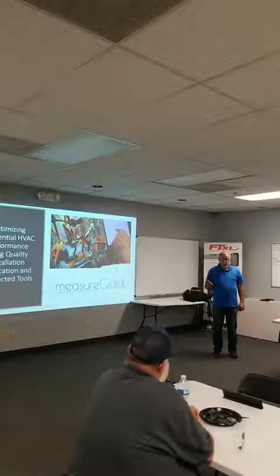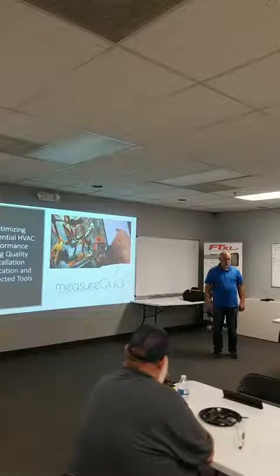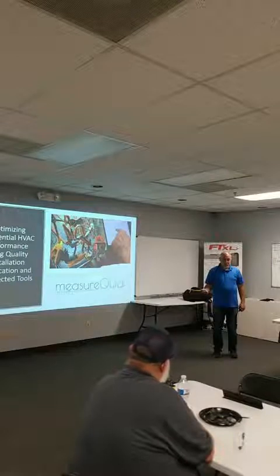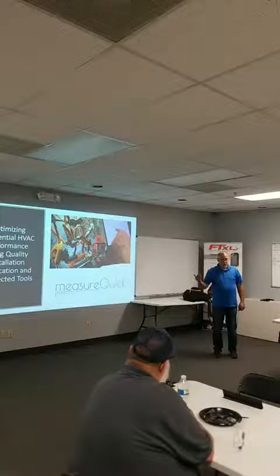If you're looking at a system with 75 degree return air, we know that typically the evaporator coil is 35 degrees colder. 75 minus 35 is a 40 degree evaporator. A 40 degree evaporator would be about 118 pounds of pressure, right? If you have a 40 degree evaporator and 10 degrees required superheat, 40 plus 10 is a 50 degree suction line temp, right? Same thing if we had a 100 degree condensing temp and were supposed to have 10 degrees of subcooling. 100 minus 10 is 90 degrees, and we'd have a 90 degree liquid line temp, right? So before you hook up your gauges, you really should understand what those numbers should be.